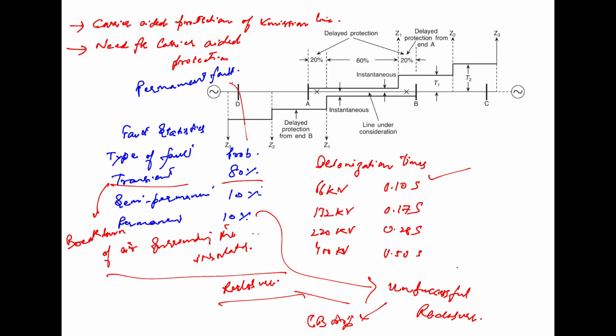Thus, in case of a transient fault, the recloser helps in keeping the downtime to a minimum and in increasing the availability of the supply. So in case of a transient fault, what is the recloser doing? The recloser helps in keeping the downtime to a minimum and increasing the availability of the supply.